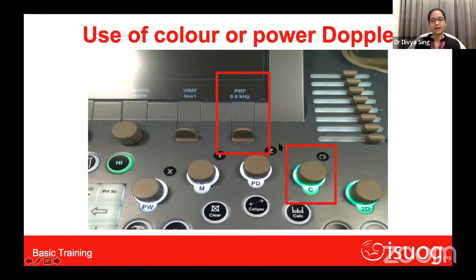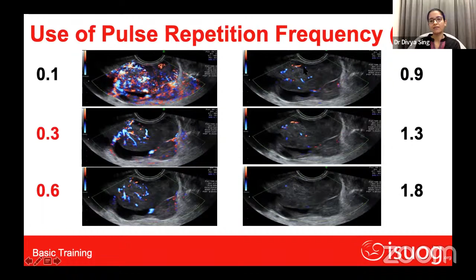If you use too low a PRF, there will be aliasing, and as a result, you would see haphazard color inside the entire color box, and even the cystic areas are showing color, which is all artifactual. Now here, if you were to see the lesion, you would give it a color score of 3, but if you were to use too low a PRF, you would end up giving a false color score of 4. So to get the correct color score, use the correct PRF settings. If you use a very high PRF, as you see here, then you will not be able to pick up the slow flow in the lesion. And here you would end up giving a color score of 1 or 2 when actually the color score is 3. So this is the importance of using the correct PRF. If it's too low, you get aliasing. If it's too high, you miss the vascularity.